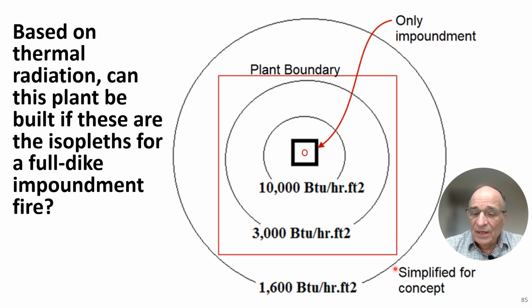But what about the 1,600 BTU per hour per foot squared? Well, for a design spill, it talked about land that can be built upon. But for a full impoundment spill, it talks about a facility or a building of public assembly where 50 or more people can exist at the time of siting. So if this is vacant land, then yes, this would meet the criteria for siting this LNG plant. But if this has a place of public assembly of 50 or more people in existence at the time of the siting, then no, this would not be acceptable by code.